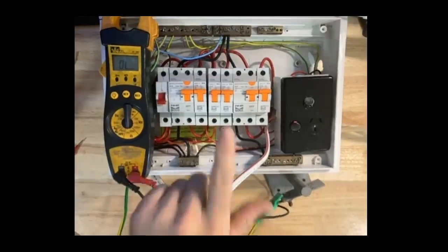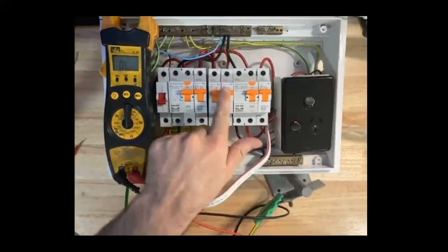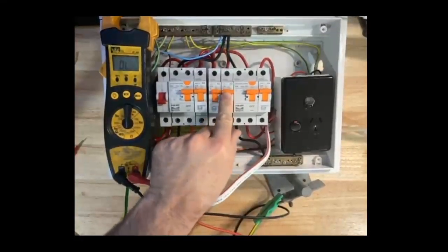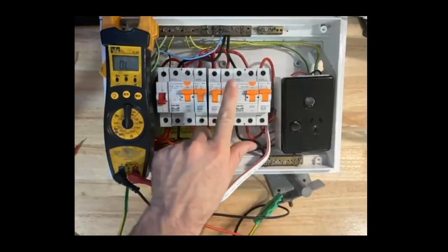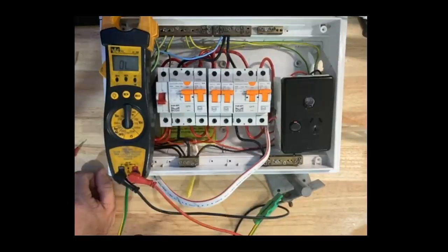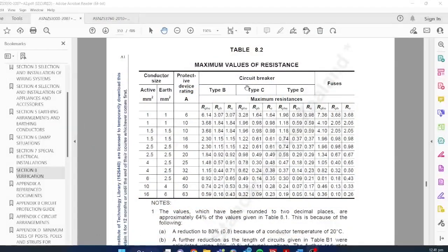And the protective device rating, if we just have a quick look there, you may be able to see that, or maybe not. It is a 20 amp C curve. If you can't see that, you'll have to believe me. It's a C20. So let's find C20 on here. So circuit breaker type C and device rating 20, conductor size 2.5 millimeters. I've got the same size active as earth conductor. So 2.5 millimeter and 2.5 millimeter, 20 amp circuit breaker type C.